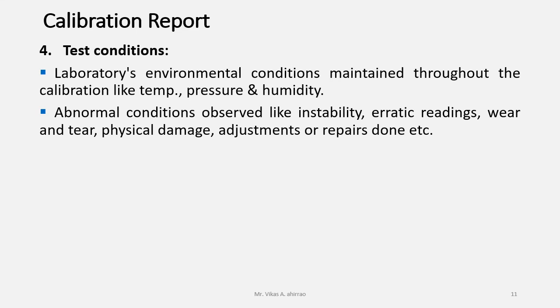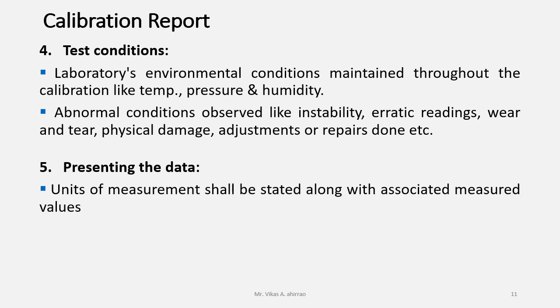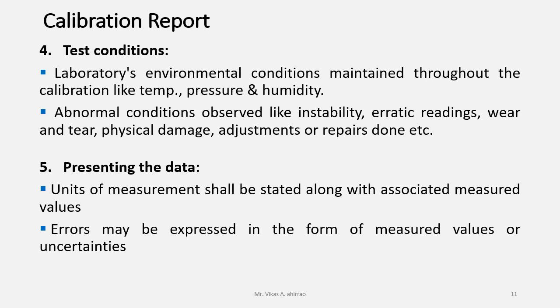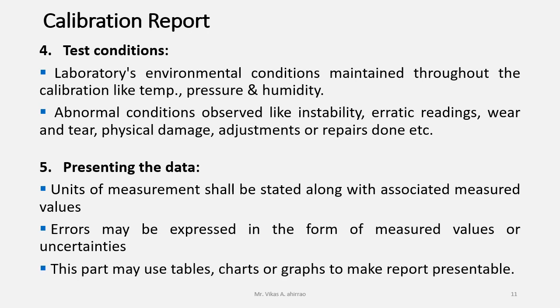Abnormal conditions observed like instability, erratic readings, wear and tear, physical damage of the instrument if observed, adjustments or repairs done, etc. Part 5 will consist of the presentation of the data. The units of measurement shall be stated along with the associated measured values. Errors may be expressed in the form of measured values or uncertainties. This part may use tables, charts, or graphs to make the report presentable.